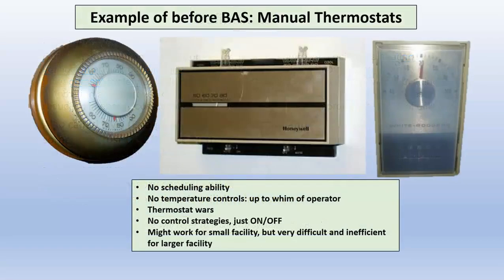All right, what did we do before we had a building automation system? How do we control temperature in a building? Manual thermostats. There's a lot of problems with these. Obviously, you can't schedule with them. You can hope people turn them off and then turn them back on, but that doesn't happen. No real controls except for the immediate temperature. It's up to the whim of the operator. You can have thermostat wars using these. If you don't believe that, go to any hospital that has 2 nursing stations with the same thermostat. No real control strategies with these, pretty much just on and off.